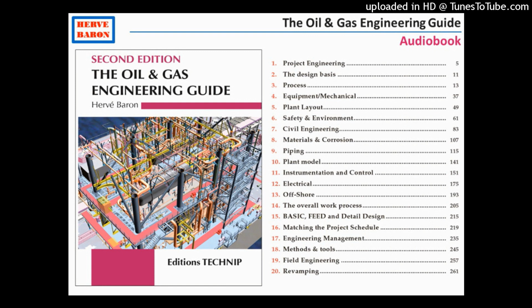The rainwater collection system, for instance, is a rather intricate collection of catch basins and pits at every change of direction to be able to clean in case of blockage. In fact, there is not only one such system, but two systems in a process plant. One for clean water, collecting the rainwater on building roofs and roads, and one for oily water, collecting water on the paving of process areas. So you see that this system of rainwater collection is rather complicated.